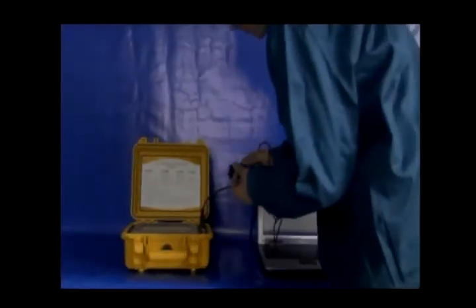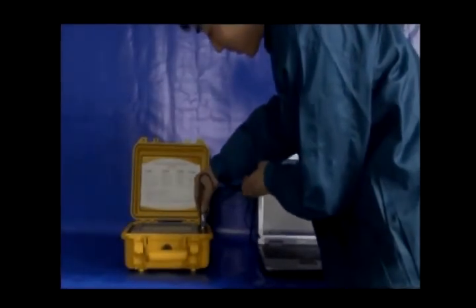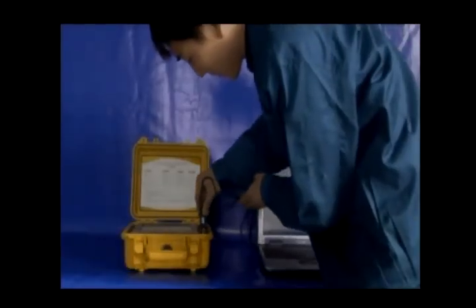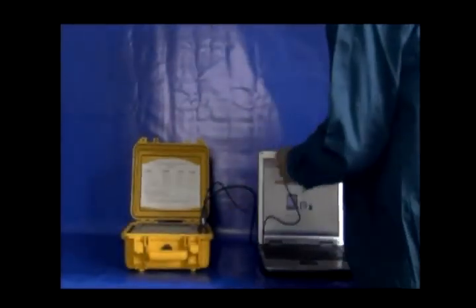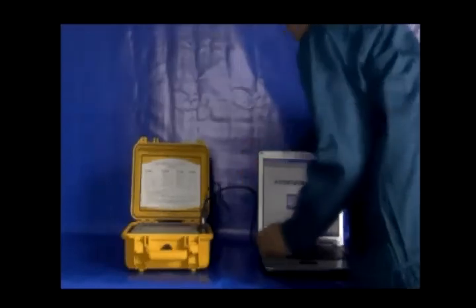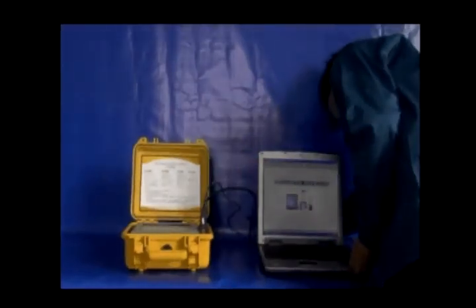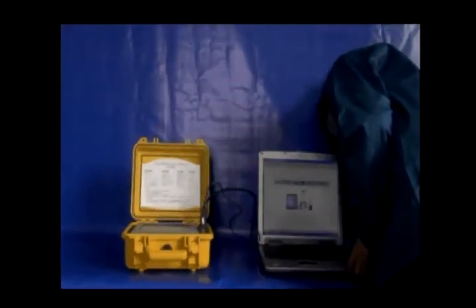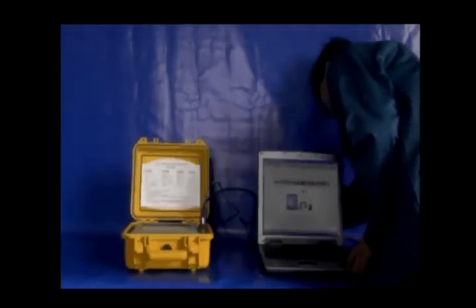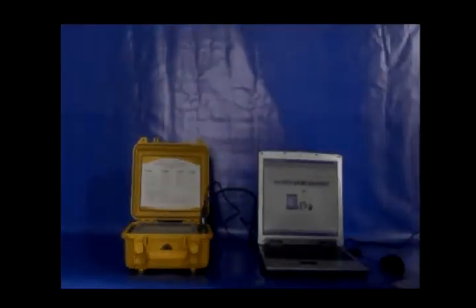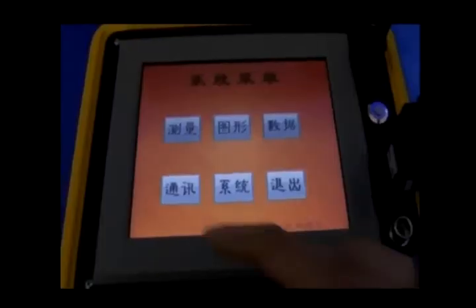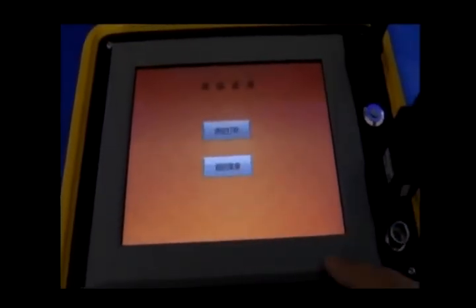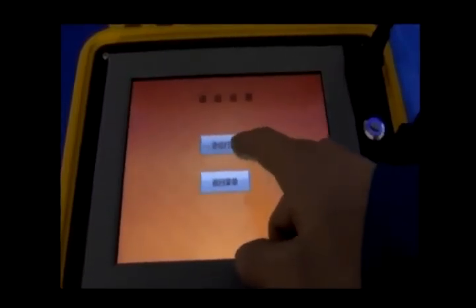Data transmission between the recording device and the external computer. The data in the recording device can be transferred to the computer, and you can work with the data through the computer. Connect the recording device to power, and then connect it to the computer's serial port RS-232.